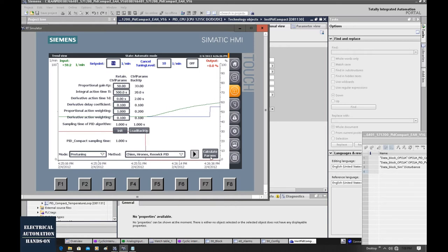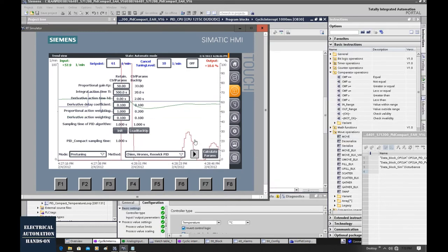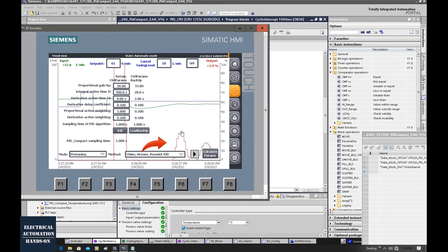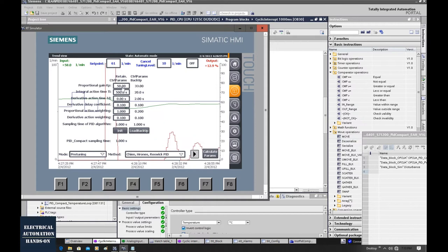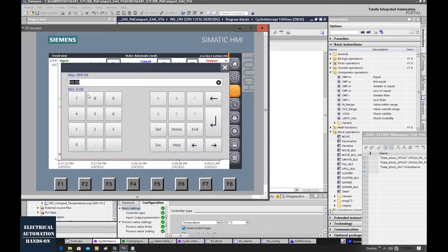Keep in mind, currently the PID is working under automatic mode. As we can see, this output will not change too much, but it gradually decreases. That means this gain is not big enough, so let's increase this gain. We need to increase this gain until the system gets an oscillation. Let's increase this KP to 80.